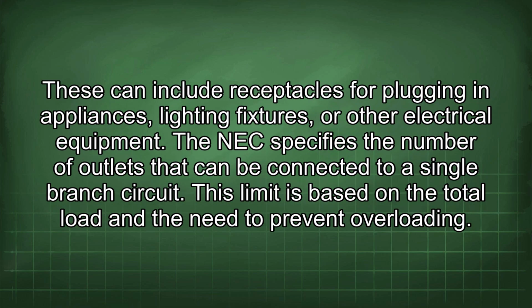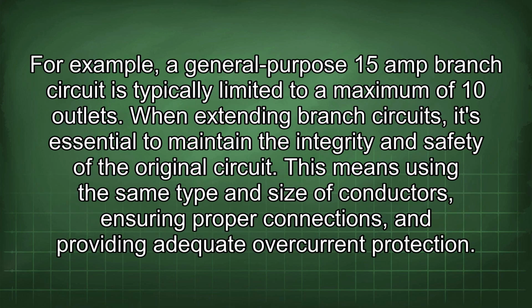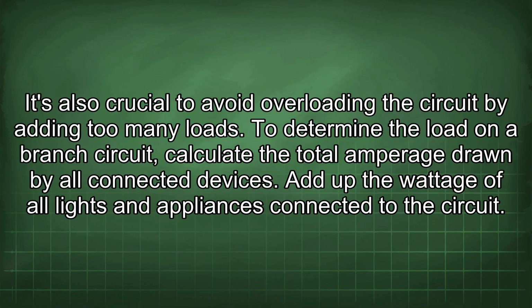Outlets are the points on a branch circuit where electrical power is drawn to supply various loads. These can include receptacles for plugging in appliances, lighting fixtures, or other electrical equipment. The NEC specifies the number of outlets that can be connected to a single branch circuit. This limit is based on the total load and the need to prevent overloading. For example, a general-purpose 15-amp branch circuit is typically limited to a maximum of 10 outlets. When extending branch circuits, it's essential to maintain the integrity and safety of the original circuit. This means using the same type and size of conductors, ensuring proper connections, and providing adequate overcurrent protection. It's also crucial to avoid overloading the circuit by adding too many loads.